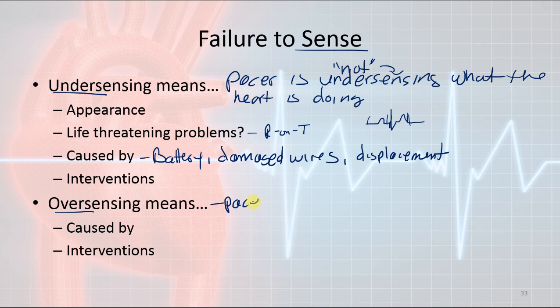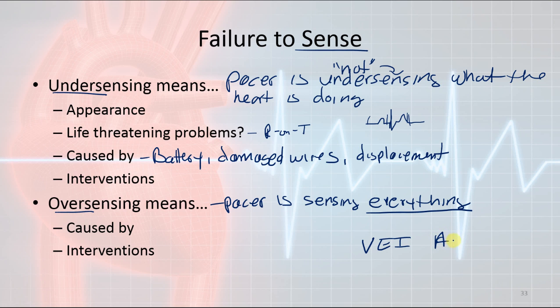Oversensing means that the pacer is sensing everything that's going on. So it will detect every little electrical anything that might occur in the body sometimes. If you ever put a person on the monitor and maybe you have some baseline artifact or some kind of artifact going across the monitor, what can happen is the pacer will sense every single little piece of artifact, and that is bad because if the pacer is using a ventricular escape interval or an atrial escape interval, every single time that it detects an electrical something, it will reset these timers prematurely. That can cause a severe drop in the patient's cardiac output and hemodynamic stability.